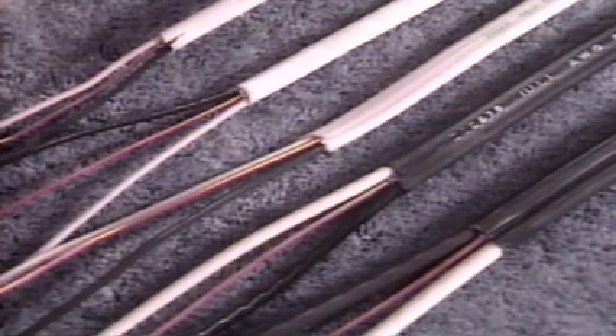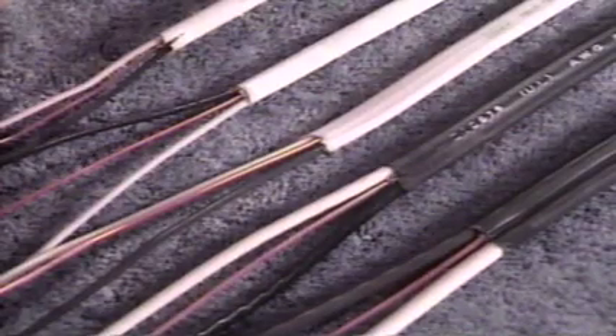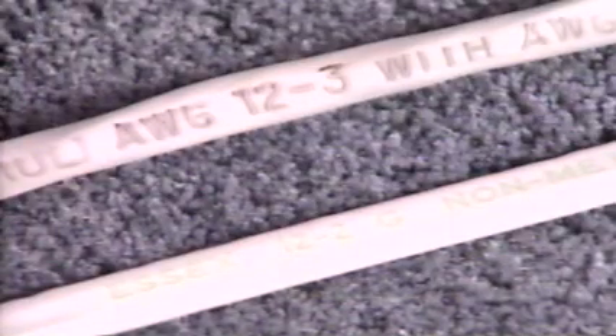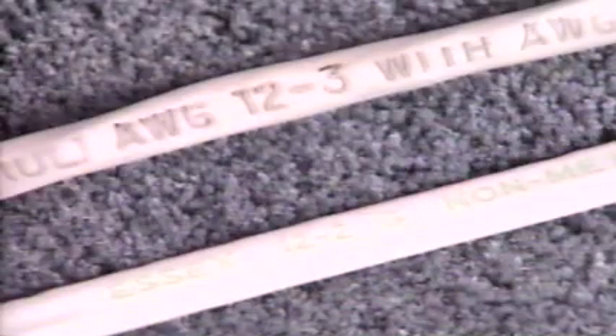This wire can range in size from number 14 to number 2 for copper wire and is available with 2 or 3 current carrying wires. These numbers stamped on the sheathing, 12-2 or 12-3, tell us that enclosed is number 12 gauge wire with either 2 or 3 conductors. The ground wire is never included in this number.